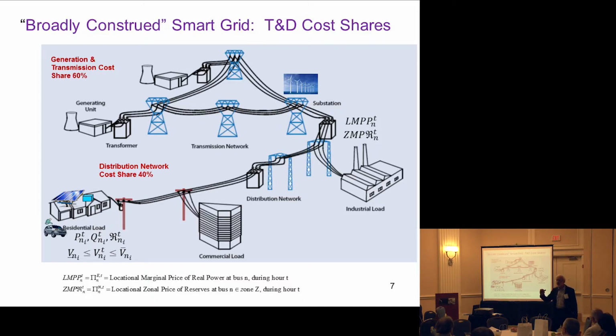So if you operate a transformer at its rated capacity, it has a 15, 20-year life. If you operate it at less than its rated capacity, its life doesn't degrade. If you operate it at a higher rate, it's like putting the double tariff or triple tariff on your taximeter. So this is a marginal cost. The decline of life is a marginal cost that reflects congestion or overloading of assets. You have higher losses that are very important here.